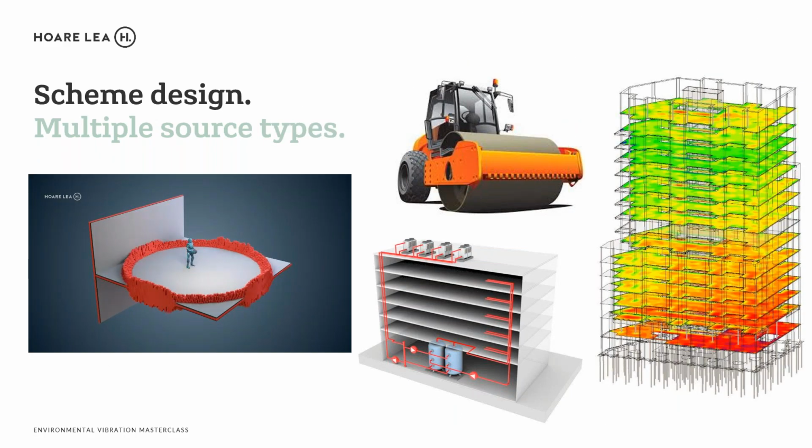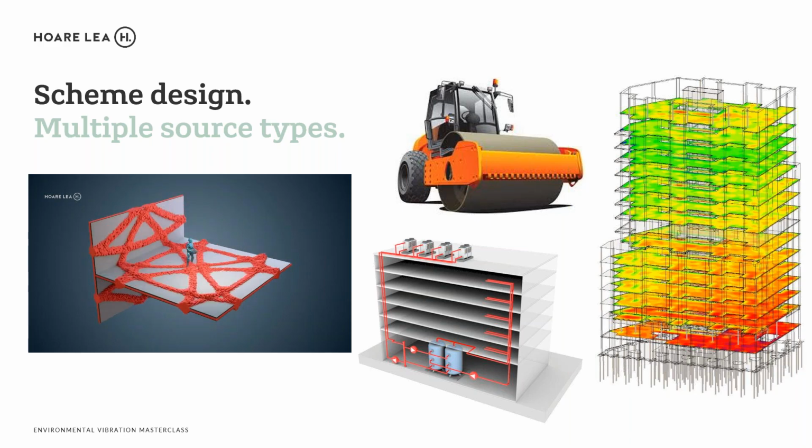Okay, so as we said at the beginning, the measurement of environmental vibration is not where the fun stops. There's lots of other things to consider. So we've got MEP sources, which are generally a big ticket item in terms of controlling vibration, especially when we're looking at facilities that are in the region of VC-E to VC-G.